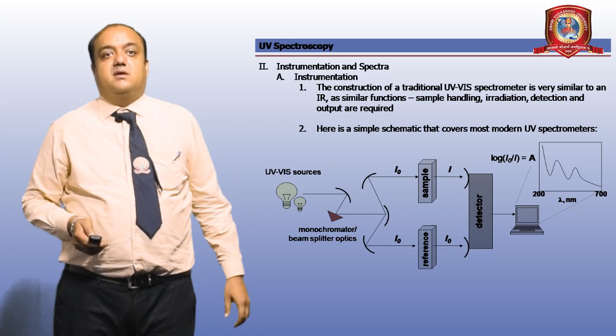This is the UV visible source. When electromagnetic radiation passes through the monochromator, then the sample, rays come in to the detector and the recorder will record the spectra. Two sources are required to scan the entire UV visible band: a deuterium lamp, which covers the UV 200 to 330 nm, and a tungsten lamp, which covers 330 to 800 nanometers. As with the dispersive IR, the lamps illuminate the entire band of UV or visible light.